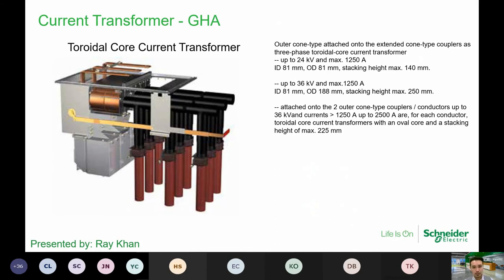It is designed and mounted inside the panel. The CTs are usually designed with cast resin, because it is designed to relieve the dielectric stress. The CT is also designed outside of the gas filled compartment. The reason it is outside is for the cable termination system. The CTs are also manufactured in the Schneider factory.